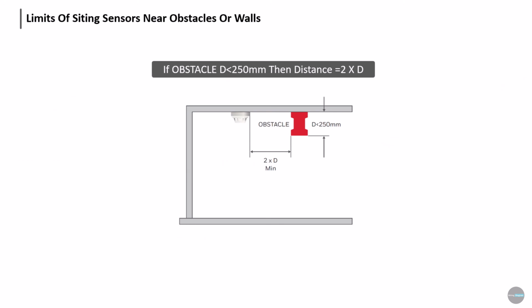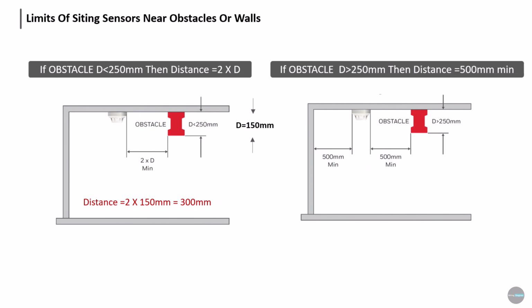1. If an obstacle such as a beam or light has a depth less than 250 millimeters, then the minimum distance between the detector and the obstacle is 2 times the obstacle depth. For example, if the obstacle depth is 150 millimeters, then the distance between the detector and the obstacle is 2 × 150 millimeters, which is 300 millimeters. 2. If the obstacle depth is more than 250 millimeters, then the minimum distance is 500 millimeters. For example, if the obstacle depth is 300 millimeters, then the distance between the detector and the obstacle is 500 millimeters.